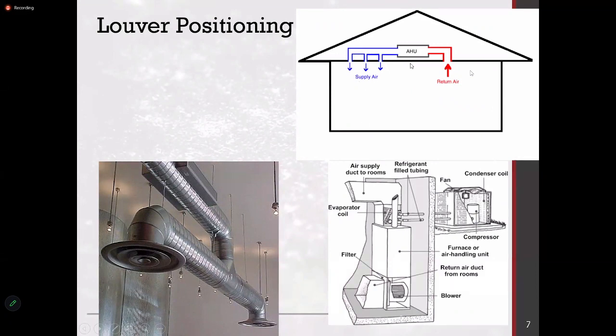Yeah, so this will be the basic arrangement in a ceiling mounted AHU, where you have a return and four supplies. Generally the return has to be larger in space, and ideally you can duct it, or if it is in multiple. So if it is in one enclosed space, there has to be at least one supply and one return. Otherwise, it will not circulate. So the return air path is also critical, just like having the outside air and the supply air.